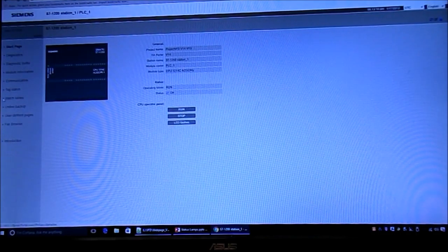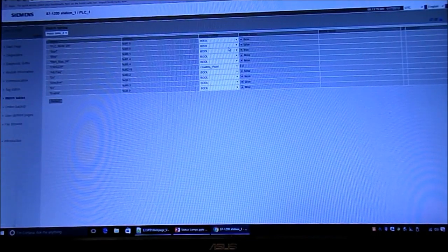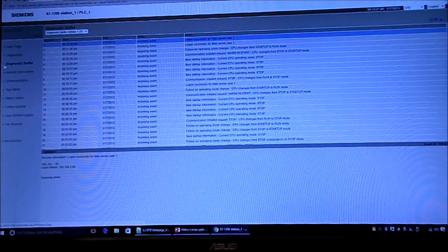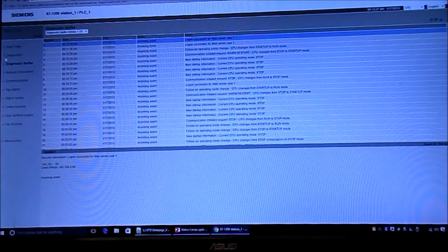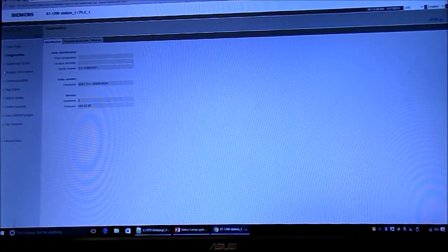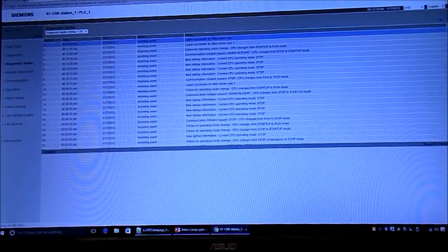Here's what I think is really good: it'll tell you what the status is, but you can also go in and look at things like a watch table. You can take a look at real time information on what your bits are set. You can also look at some of the diagnostic buffers for what you have in diagnostics.